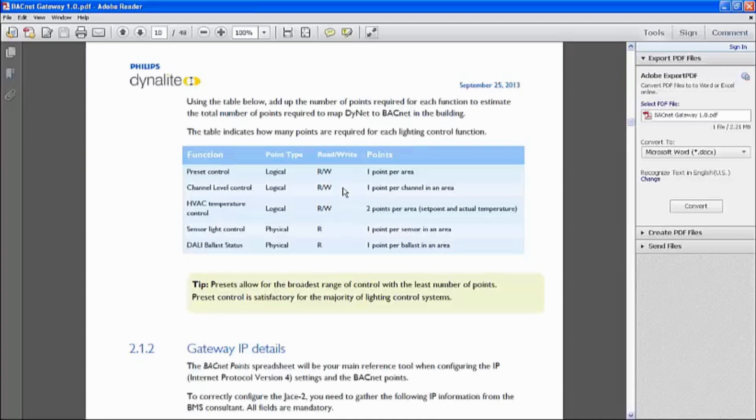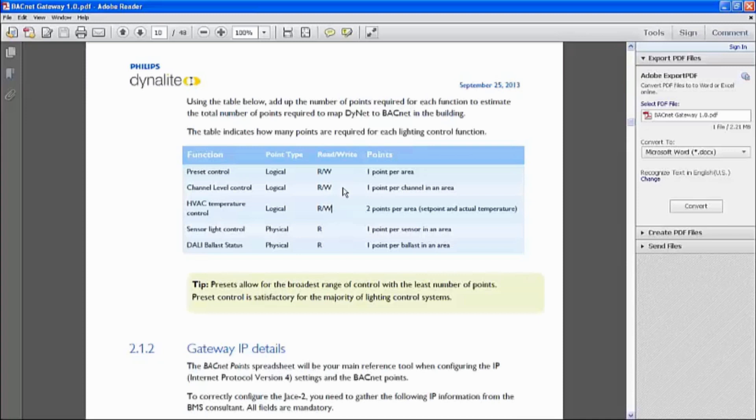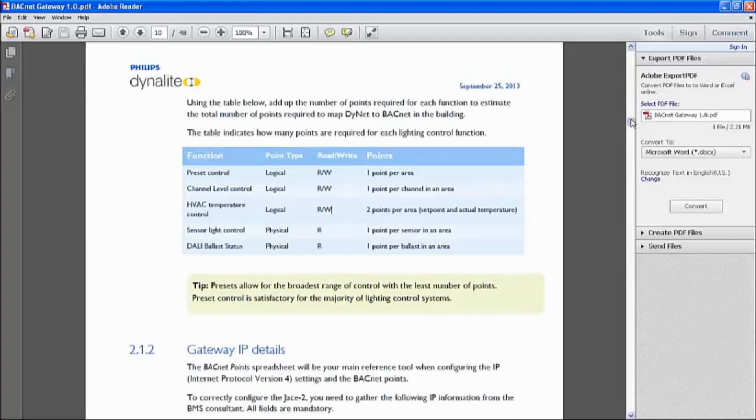Light level and DALI ballast are not two-way communication. It's only a read from the BMS site. So what they do is they'll just request what's my value, and then we'll provide them the current lux level of this particular area, or this particular sensor is so many lux, and probably a ballast status, ballast offline, lamp failure, and so on and so forth.